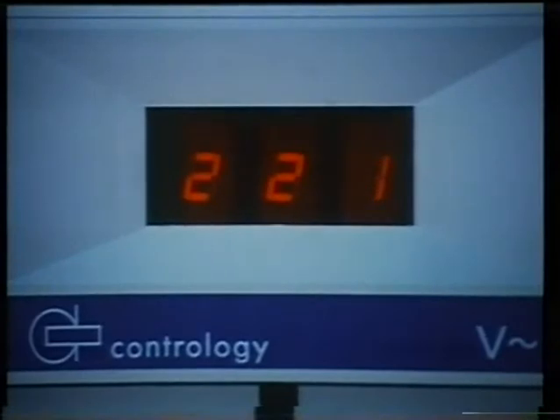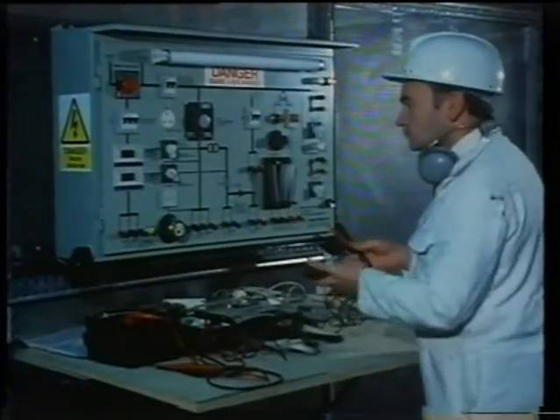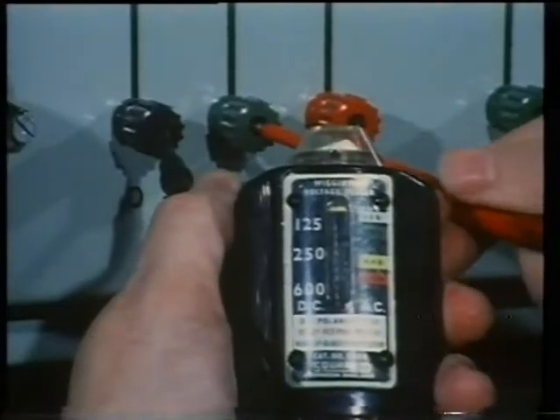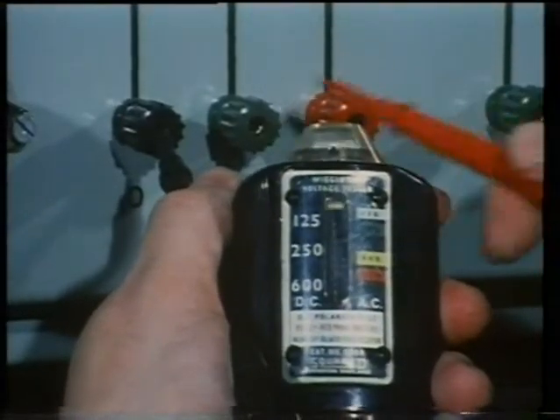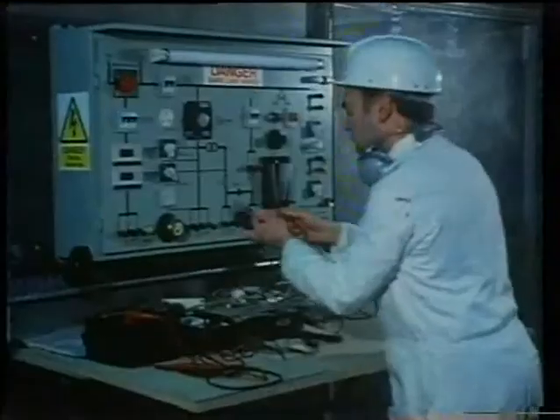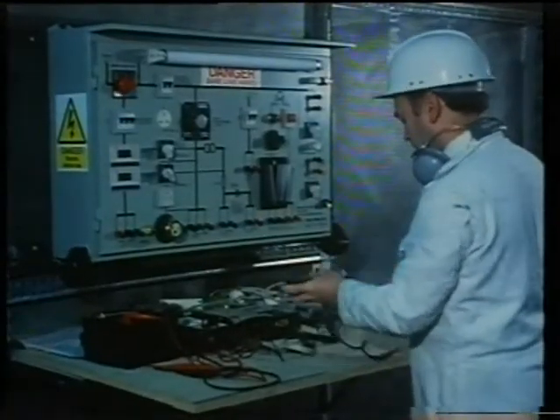Finally, a line tester, set to test for the presence of 220 volt supply. First, the voltage on the test panel is set. Then the line tester, or a multimeter for that matter, is tested for correct function. These test instruments are all used for monitoring the condition of electrical installations or for assisting with fault diagnosis or fault finding.